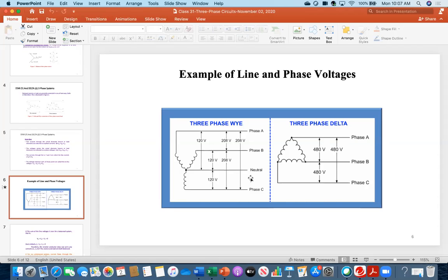So you all know that the neutral is ultimately connected to the grounding system, like at your home. So therefore the neutral line is connected to the grounding system for the safety purpose. But you see, here there is no neutral. So this means this connection is not safe for people's use. That's why typically the delta connected systems are not used in home or even in industry. Those are mostly used only along the overhead line.